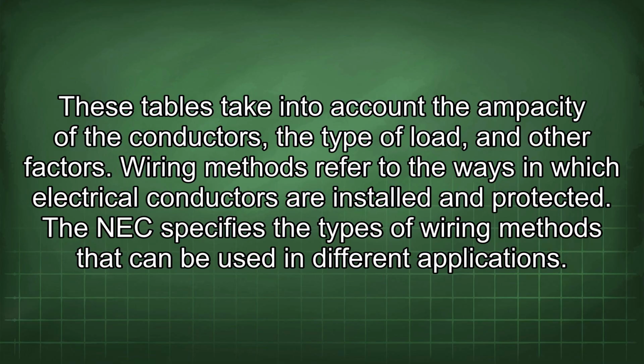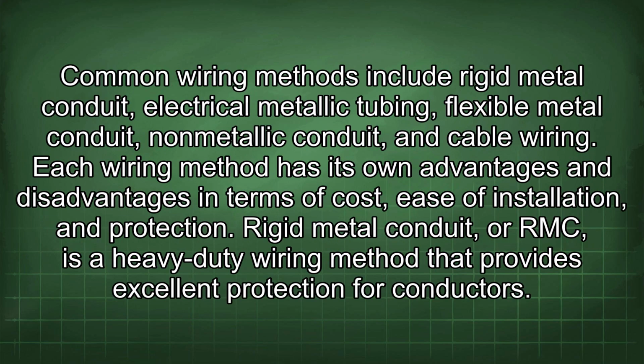Wiring methods refer to the ways in which electrical conductors are installed and protected. The NEC specifies the types of wiring methods that can be used in different applications. Common wiring methods include rigid metal conduit, electrical metallic tubing, flexible metal conduit, non-metallic conduit, and cable wiring. Each wiring method has its own advantages and disadvantages in terms of cost, ease of installation, and protection.